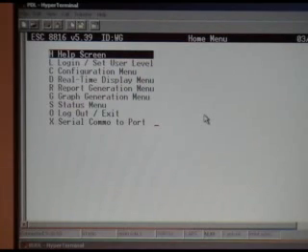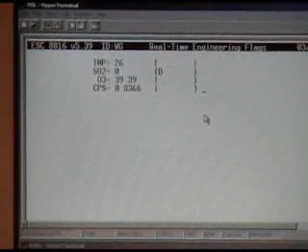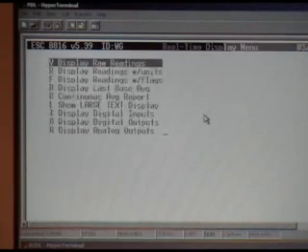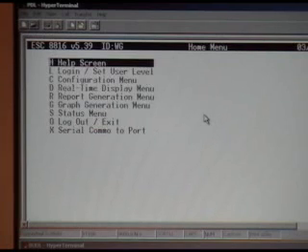Just to make sure that it's not flagged, we're going to hit DF. You can see the only channel down right now is the sulfur channel. Escape. We'll do the same for the backup. And now that those channels are up, cal is stopped.